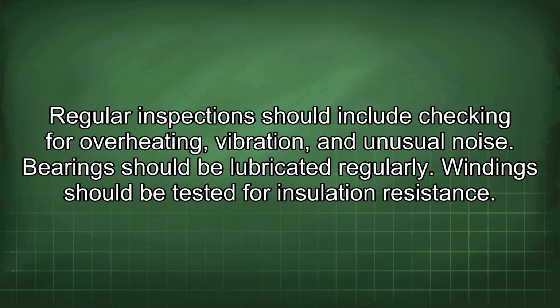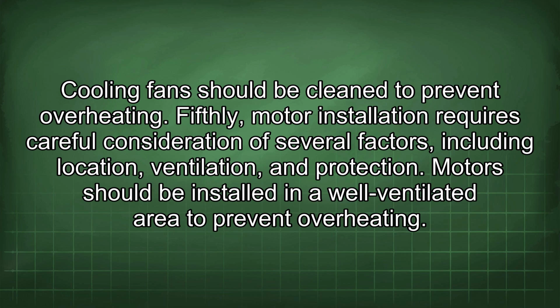Regular inspections should include checking for overheating, vibration, and unusual noise. Bearings should be lubricated regularly. Windings should be tested for insulation resistance. Cooling fans should be cleaned to prevent overheating. Fifthly, motor installation requires careful consideration of several factors, including location, ventilation, and protection.